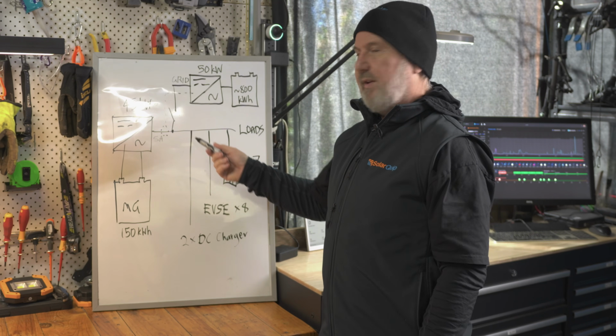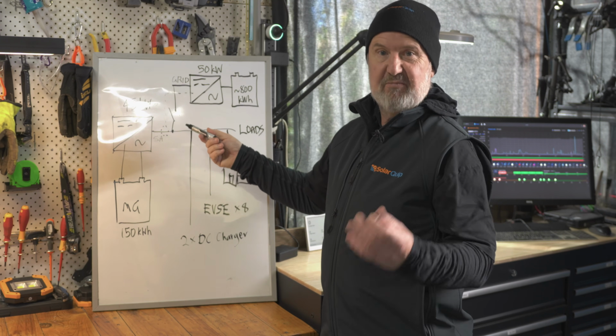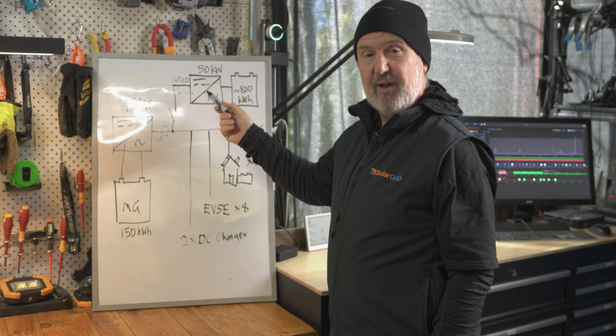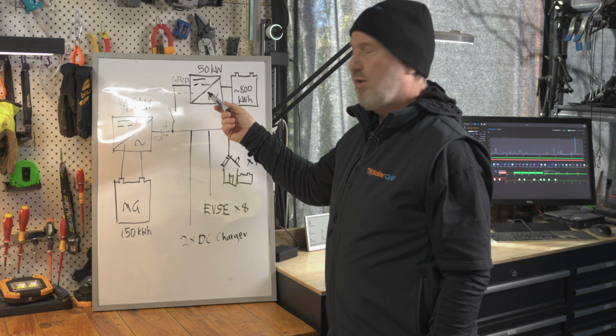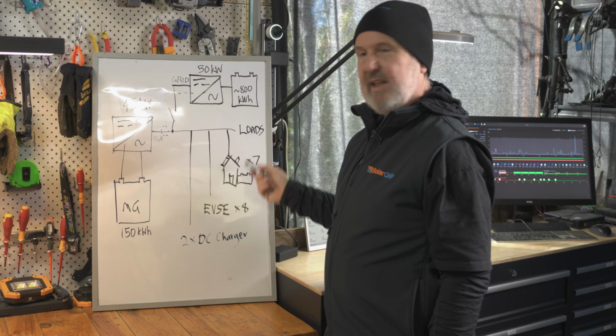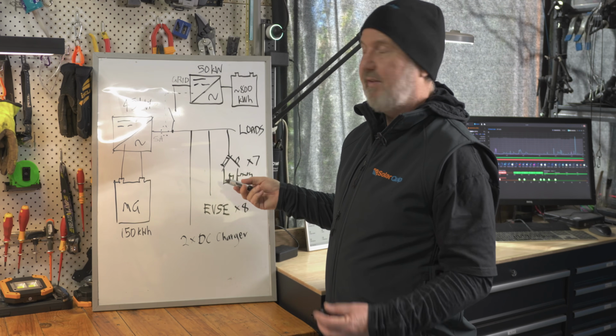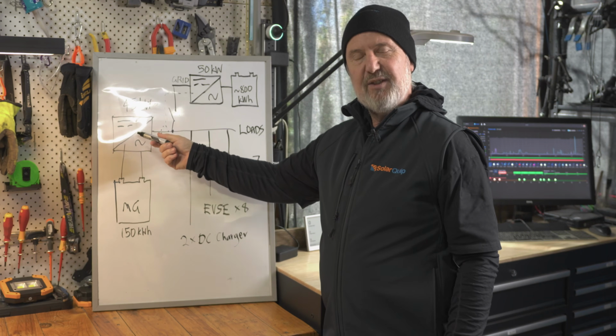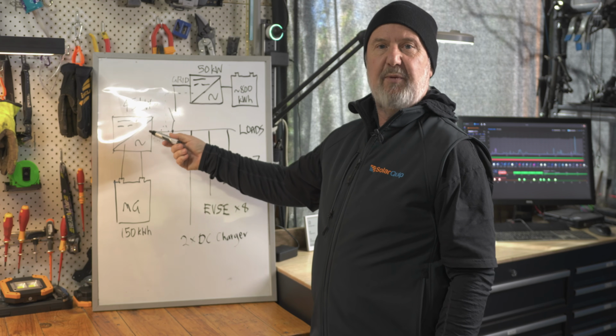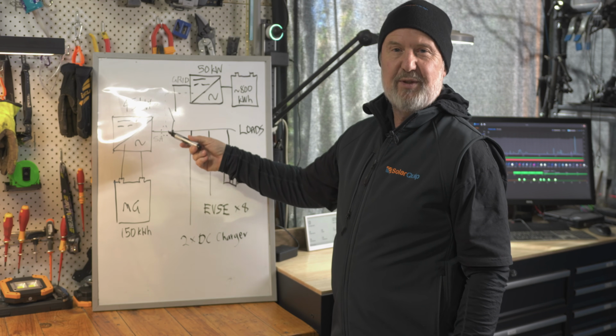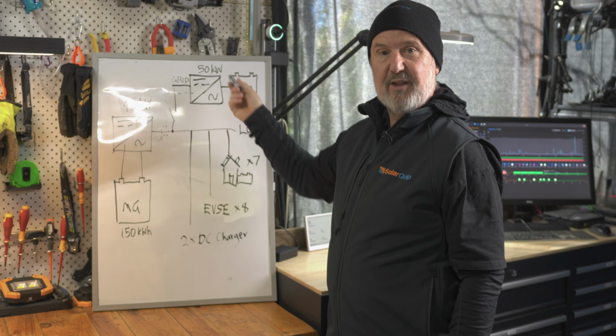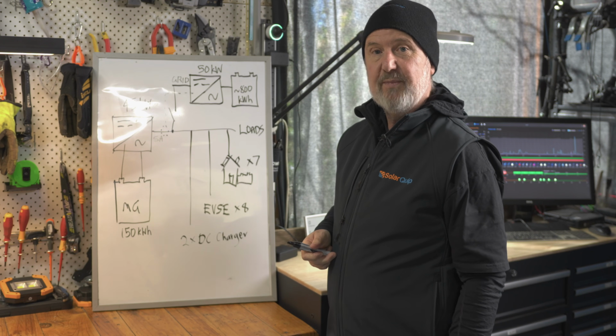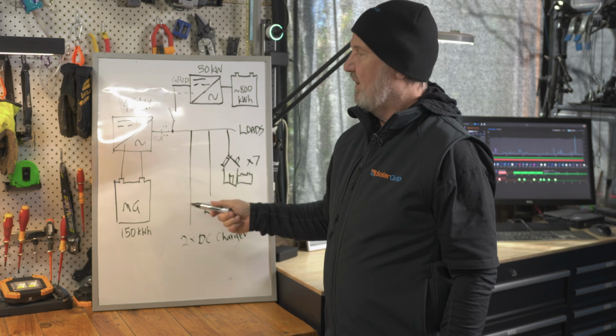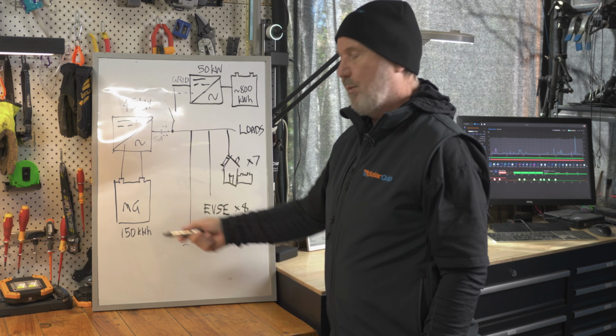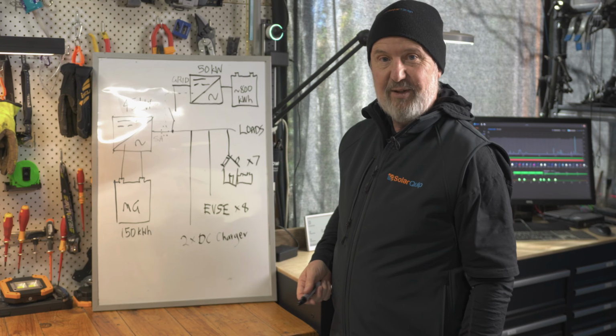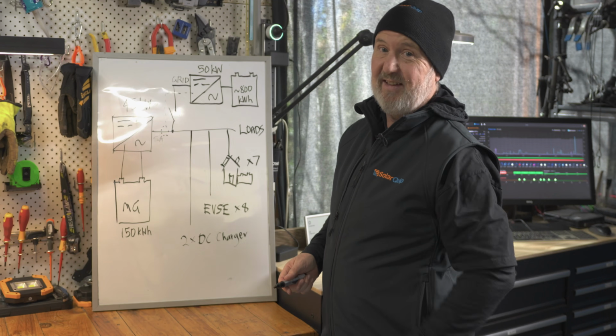And whenever it's drawing 10 kilowatts, the first one to try and supply that is the Solis. So the Solis tries to jump in there and provide the 10 kilowatts to run the loads, or the 50 or whatever. This is really here just as a voltage source to provide a synchronization, frequency and voltage for this to synchronize with, because this is effectively in grid connect mode, whereas this is in standalone mode. So this is AC coupling, more storage. So we started with 150, we've added another 800, nearly a megawatt hour. I like the sound of that.